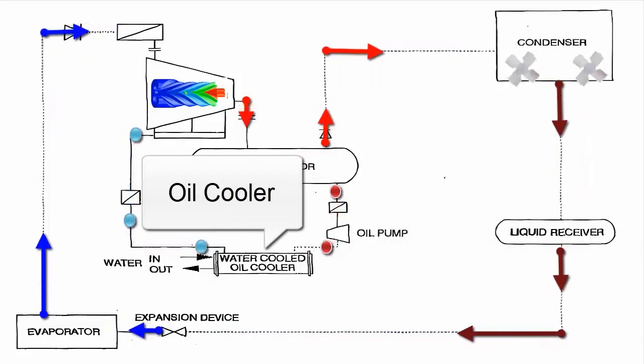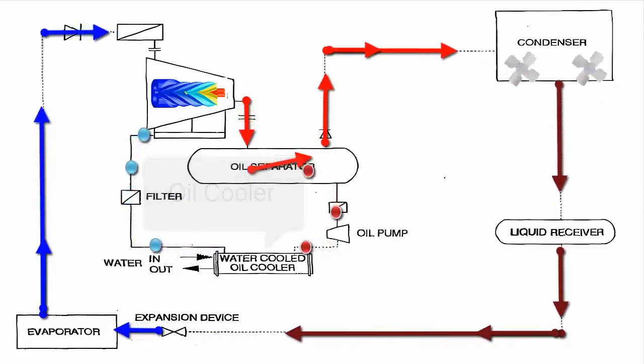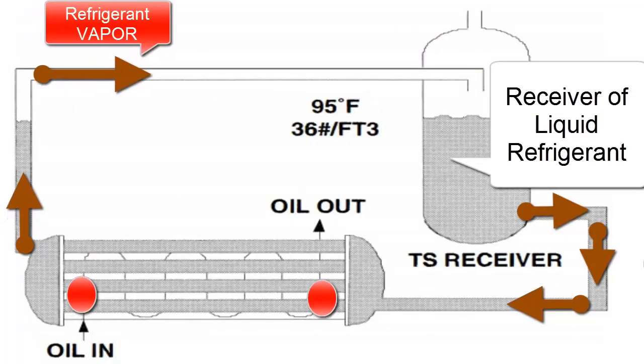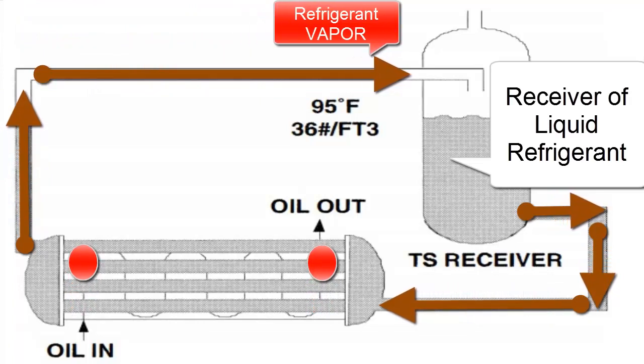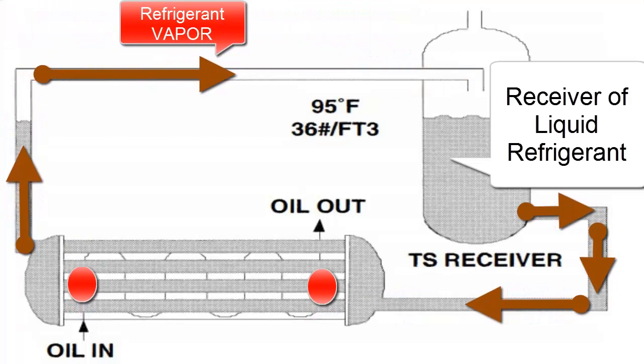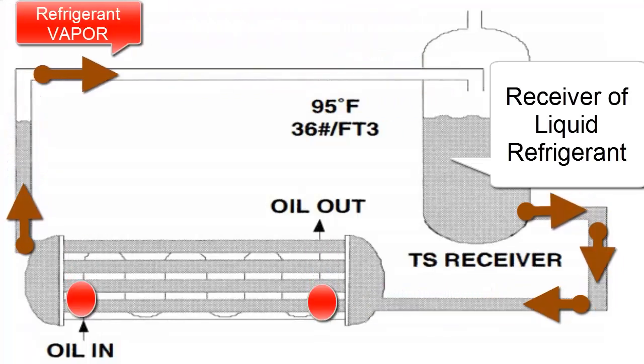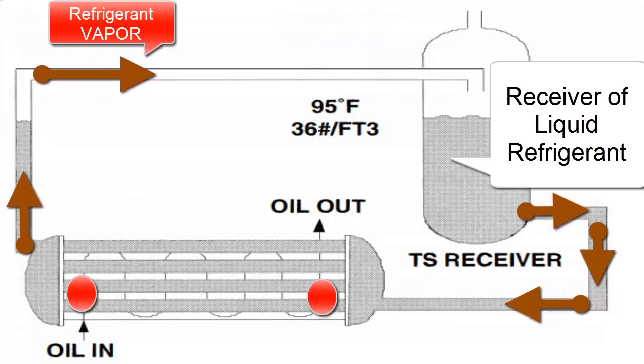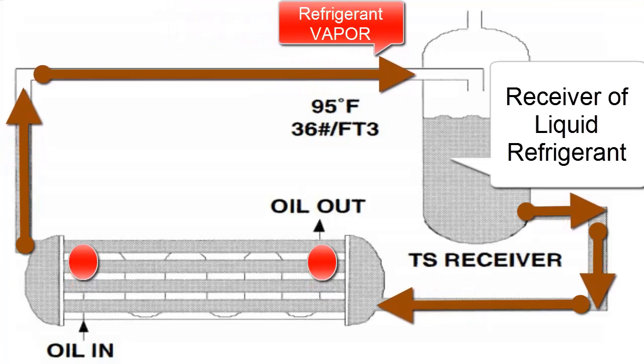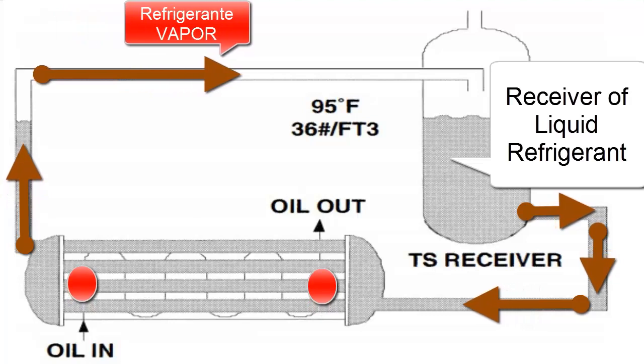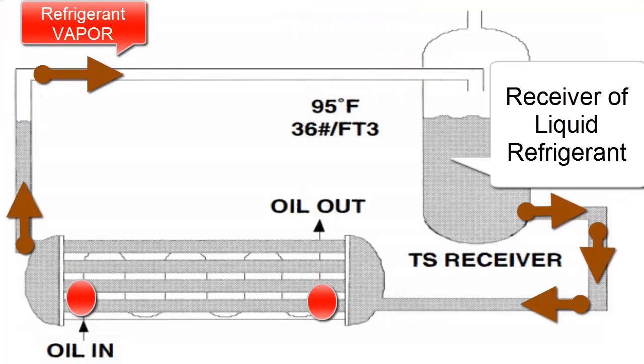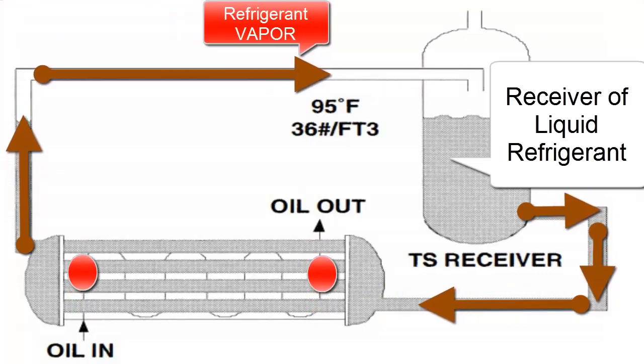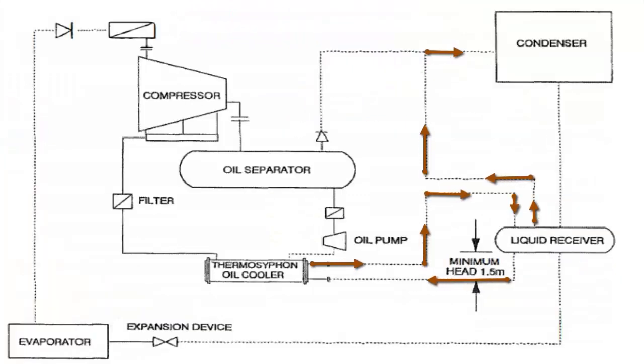Oil Cooler. The oil can be cooled in an oil-water heat exchanger. However, oil cooling by thermosiphon is the most common method of external oil cooling. The system is similar to a water-cooled system, except that water is replaced by the same refrigerant from the circuit coming from the condenser. This method uses high-pressure liquid refrigerant from the condenser to remove heat from the oil. As the hot oil enters the shell side of the heat exchanger, the liquid refrigerant absorbs heat from the oil and boils, rising back to the receiver. The vapor generated by this process is sent back to the condenser inlet, where it releases heat and returns as liquid to the system. In effect, the operating principle of this exchanger is the same as that of the gravity-flooded evaporator. Thermosiphon systems are popular because they require virtually no maintenance.